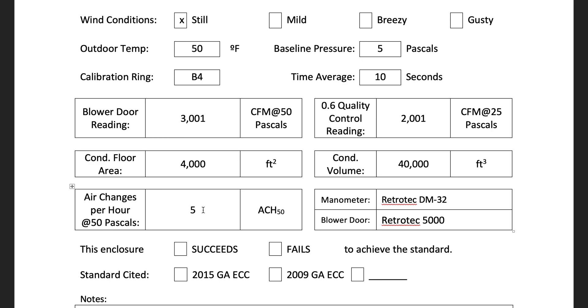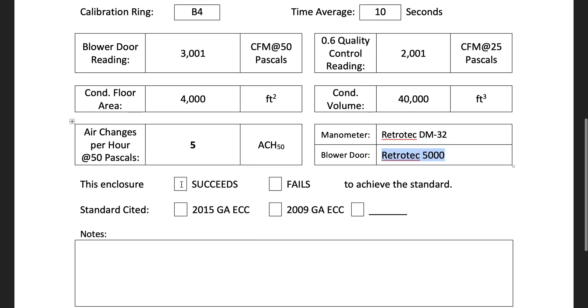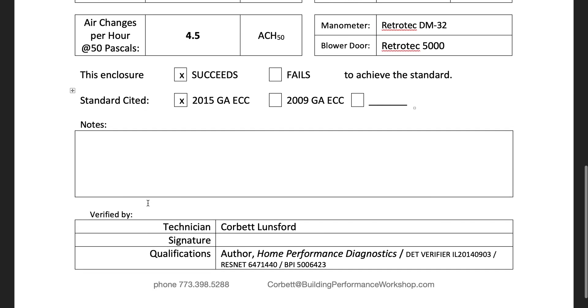Code says 5 — not 5.0 — so just make it easy on the code official and put one round number. You can bold it or color it red to make it clear. You are free to edit this report template however you like. But if you put the decimals in there, somebody might get a hard time later. Likewise, 4.5 rounds up to 5. So if you're beating code, go ahead and put in the decimal places so they know. Put in what manometer model and brand you're using and what blower door fan you're using, then simply tell them whether it succeeds or fails. For example: 2015 Georgia Energy Conservation Code. Your state will have its own amendments, so make sure you know what that is.